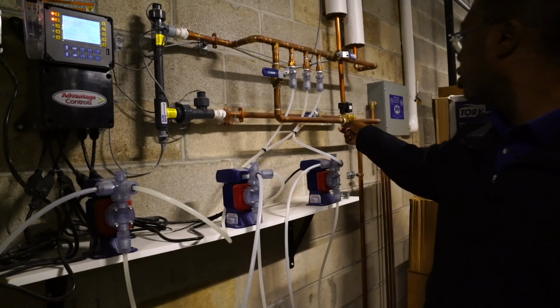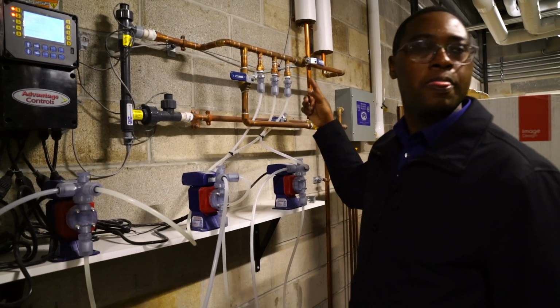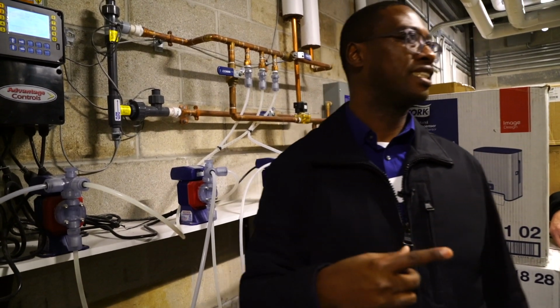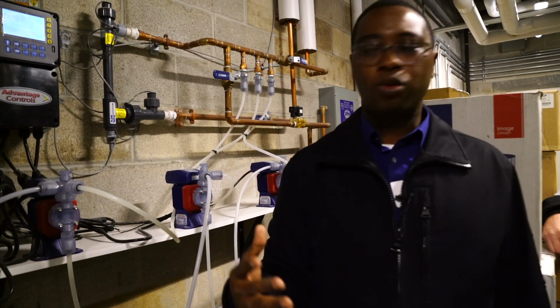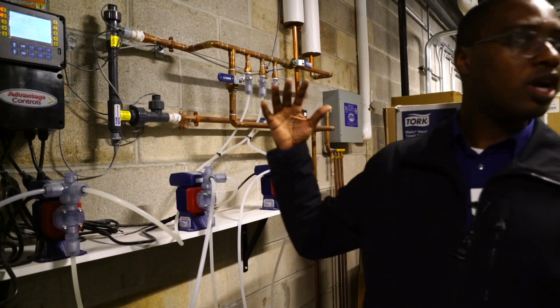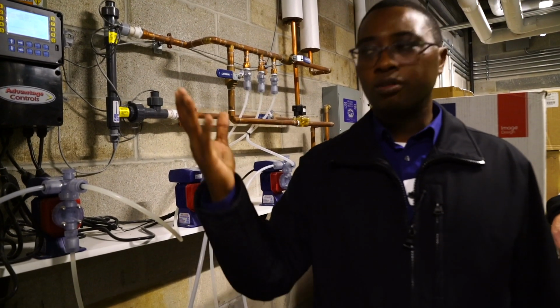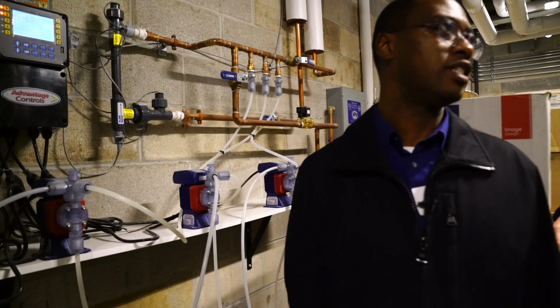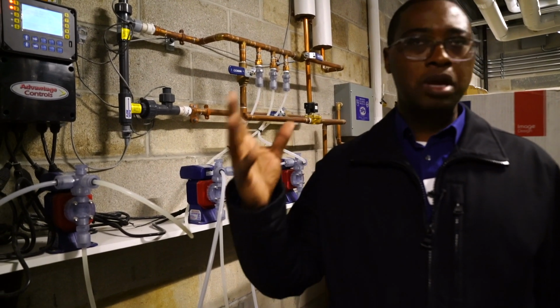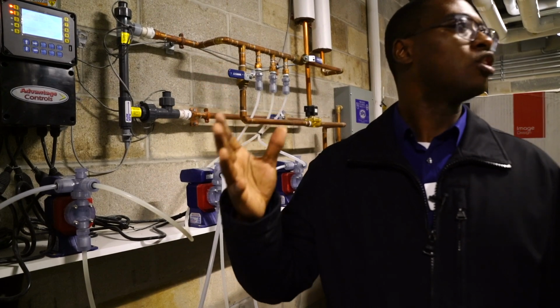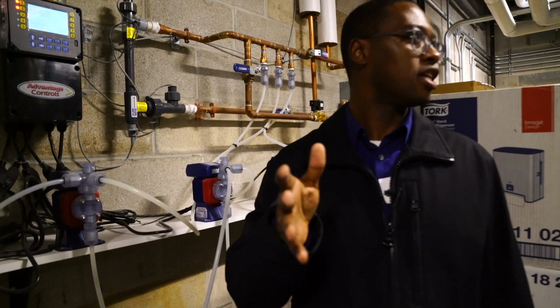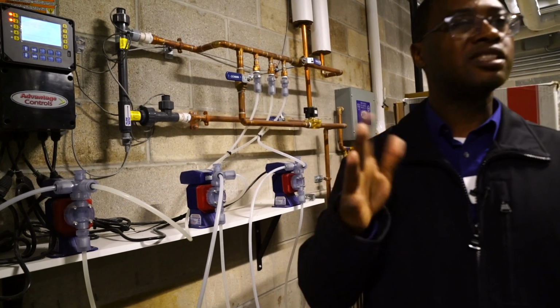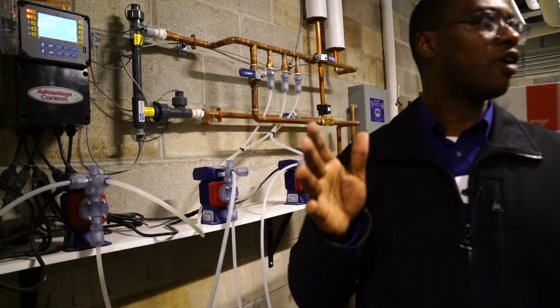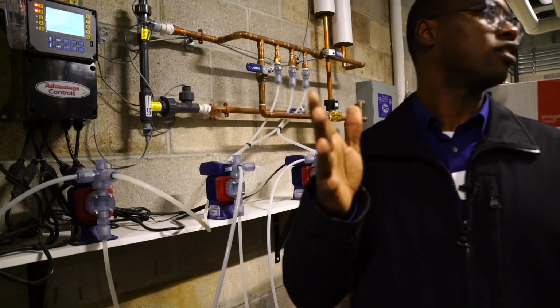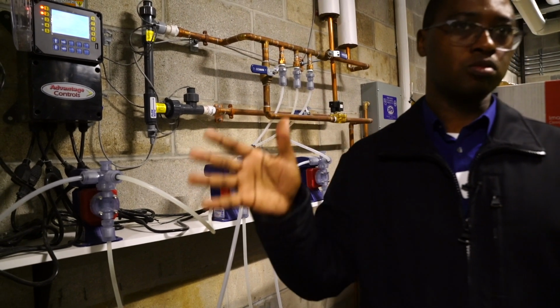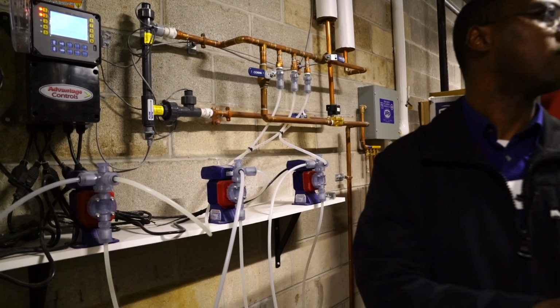Right. So this is what maintains what we call cycles of concentration. Why cycles of concentration? Because water comes in with a certain TDS, in this area maybe 300, 400 TDS. We cycle it maybe 4 times. So we say, okay, 4 times 400, 1,600. If it's 1,600, we're not building scale, that's fine. But I would usually go to 1,200. So we're cycling it 3 times before we blow down.